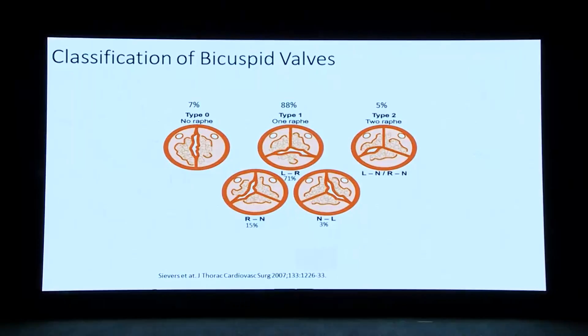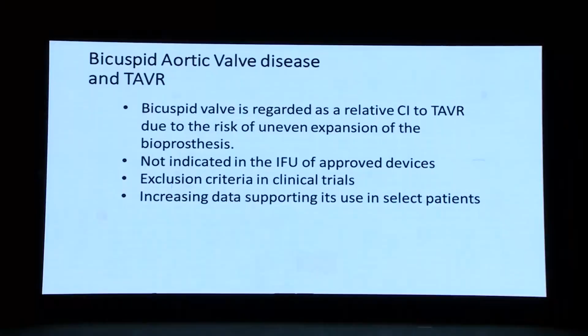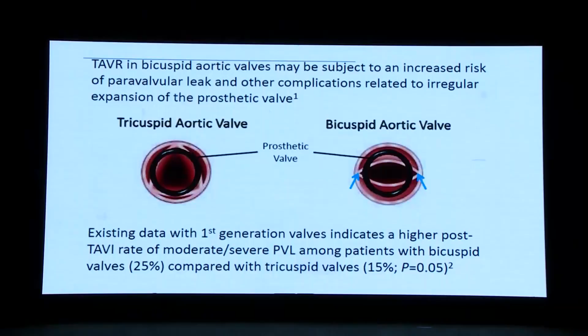Next slide. Bicuspid aortic valve was considered a relative contraindication, and in fact it's an off-label indication. It is not even indicated in the IFU of approved devices, because it was not included in the trials. Now more and more data is supporting its use. Next slide. The challenge is, if it is a tricuspid aortic valve, the prosthetic valve will open uniformly. Whereas in a bicuspid valve, the orifice is elliptical, and hence when we use a circular valve, at the sides it may not close completely and can result in paravalvular leak.